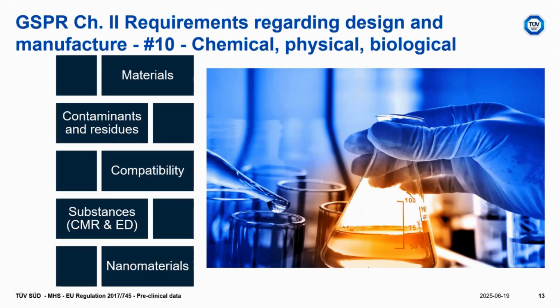There is a requirement that not all the core materials, where you can say my device is made of this and this, but there is an expectation to have the definition also of the contaminants and the residues which are coming from the full production process, including those that are not intended to be part of the final device but that can have the potential to remain on the device because of the production process. So we expect a very, very well detailed assessment of all the contaminants and the residue.